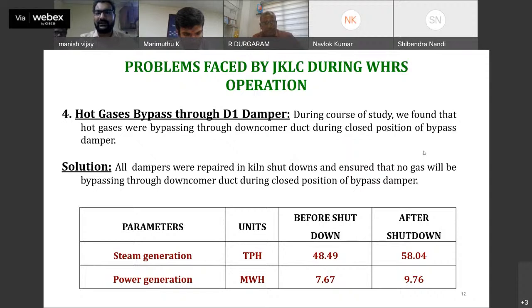Fourth one is the bypassing. In the bypass, we have multi-louver dampers, so the sealing of that damper is not such that it seals 100% of the gases. So by doing brainstorming sessions and using the experience of our mechanical engineers, we decided to put a plate above the flanges of the damper, so that during the closed condition, no gases will be bypassed through this damper. By doing this, we got a tremendous result in generation of the power, and the power generation is around 30% higher by sealing of the damper from the PH side.